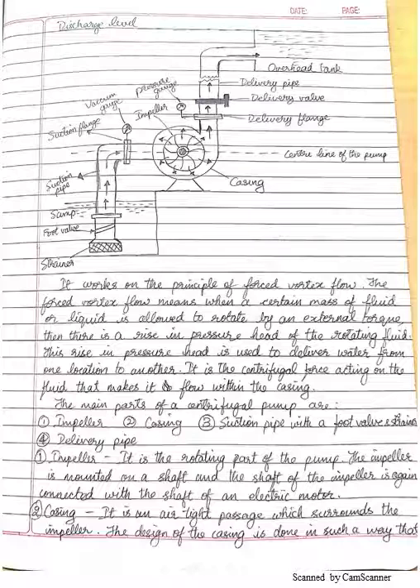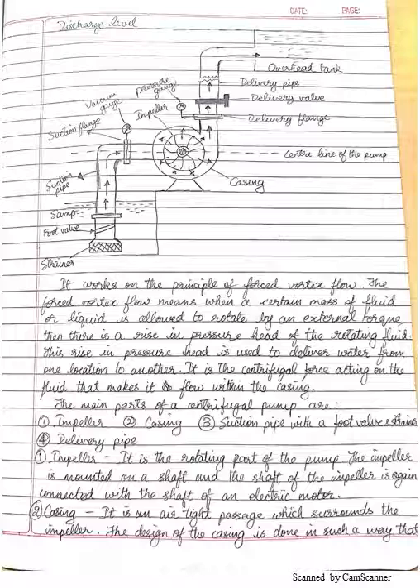The centrifugal force acting on the fluid causes suction, and water from the sump moves upward through the suction pipe onto the suction flange, into the casing, then upward through the delivery flange, through the delivery valve, onto the delivery pipe, and finally to the overhead tank. The main parts are the impeller (the rotating section), the casing which covers the impeller and provides protection, and the suction pipe with a foot valve and strainer, along with the delivery pipe with delivery flange and valve.